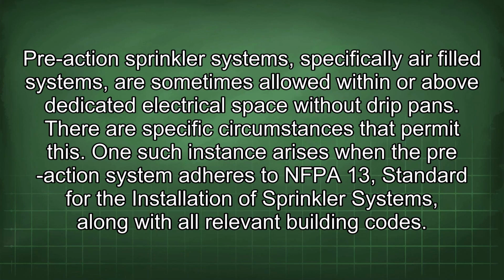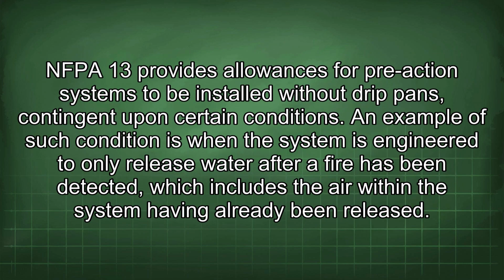Pre-action sprinkler systems, specifically air-filled systems, are sometimes allowed within or above dedicated electrical space without drip pans. There are specific circumstances that permit this. One such instance arises when the pre-action system adheres to NFPA 13, the standard for the installation of sprinkler systems, along with all relevant building codes. NFPA 13 provides allowances for pre-action systems to be installed without drip pans, contingent upon certain conditions.